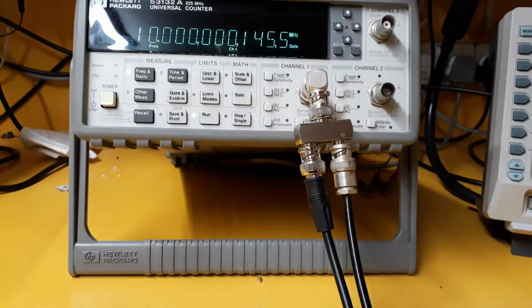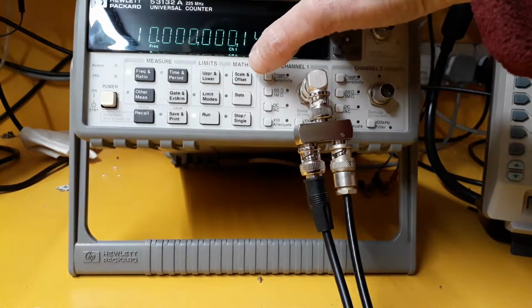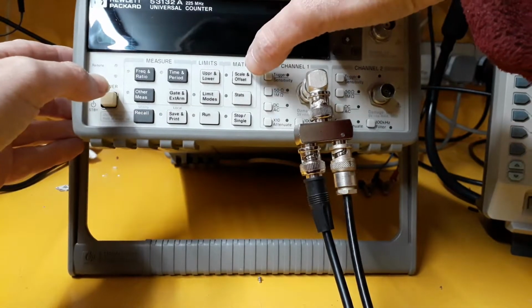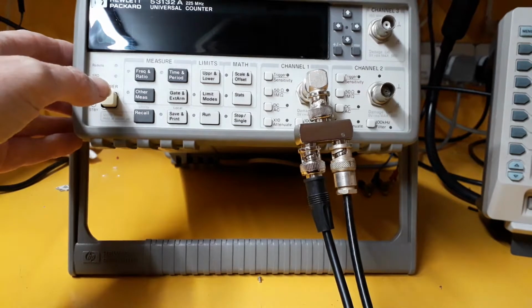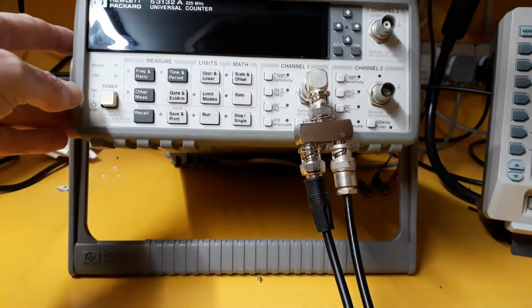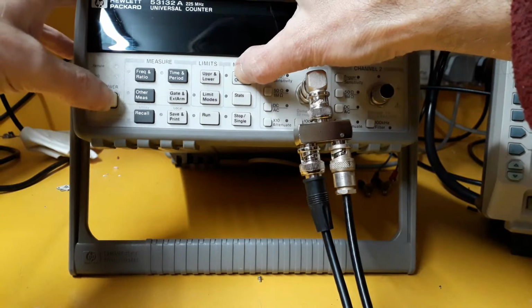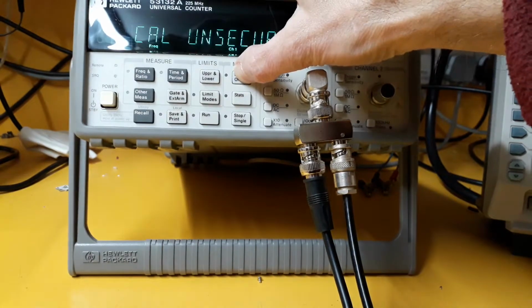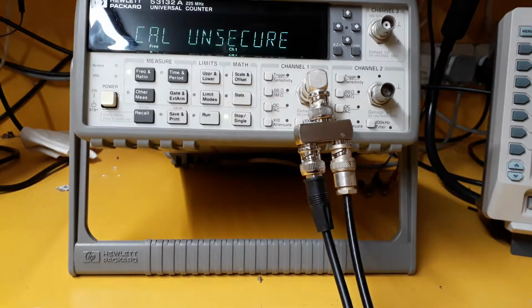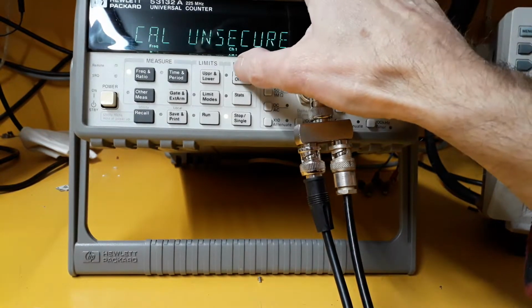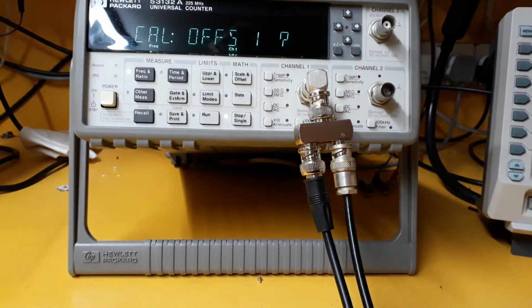0.14 hertz difference. So I'll just try and get into the calibration menu. I'm trying to remember how you do it. Right, I think you have to turn the power off, and that doesn't affect the oven, it's still connected all the time when the thing's plugged in. Then you press scale and offset and hold that down and turn the power back on, and it says cal unsecure, so I don't have to unlock it, in other words. And then I think you press scale and offset again, yeah, and then you get a calibration menu.